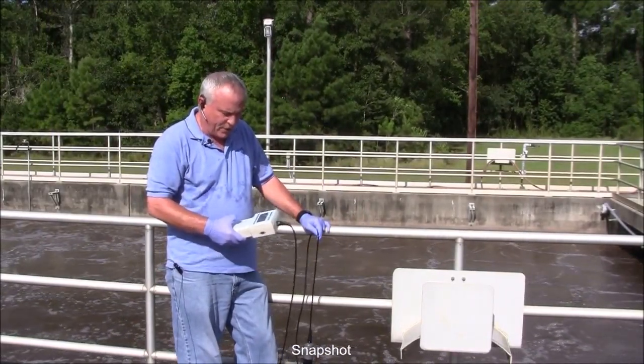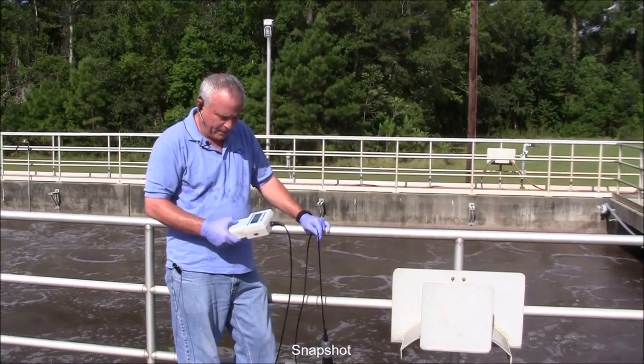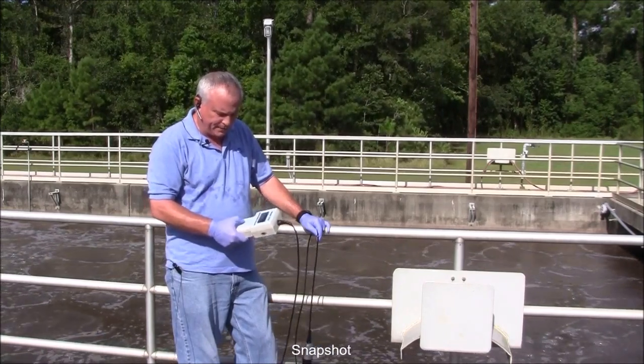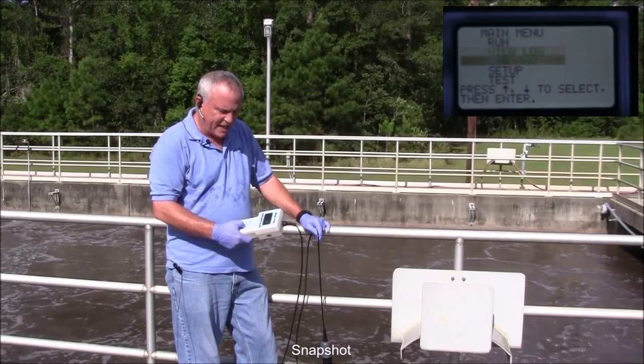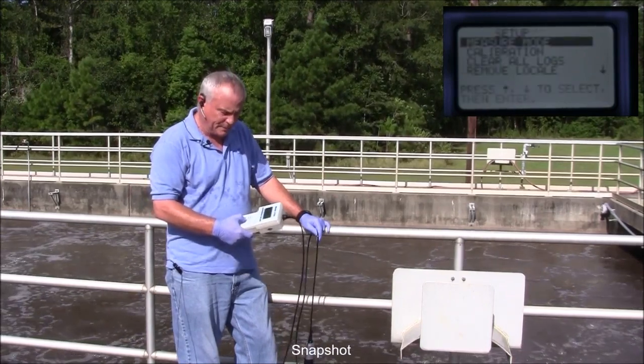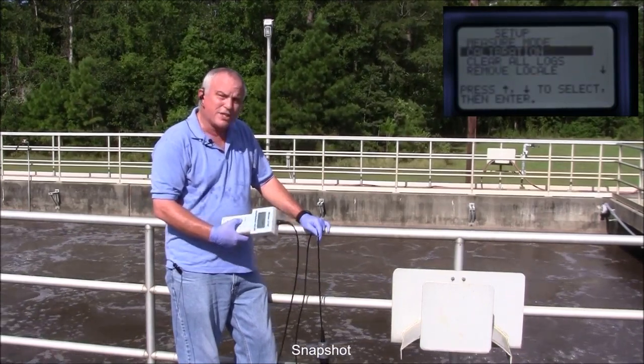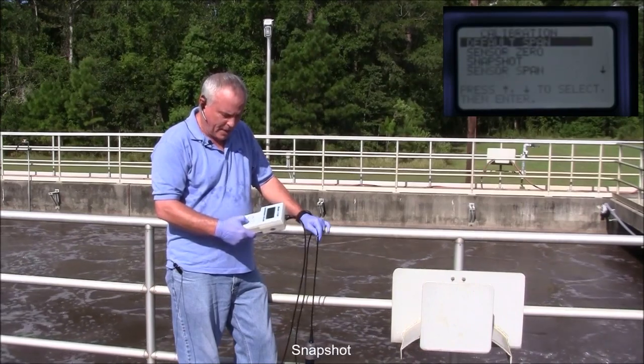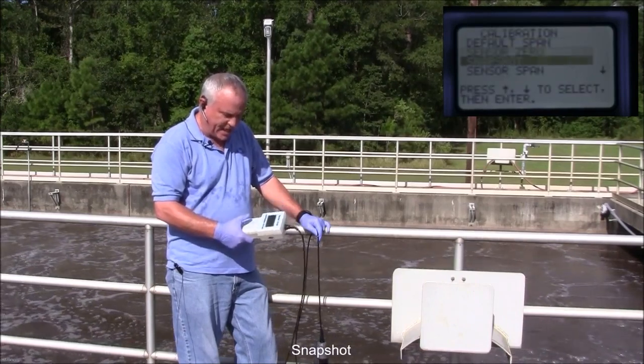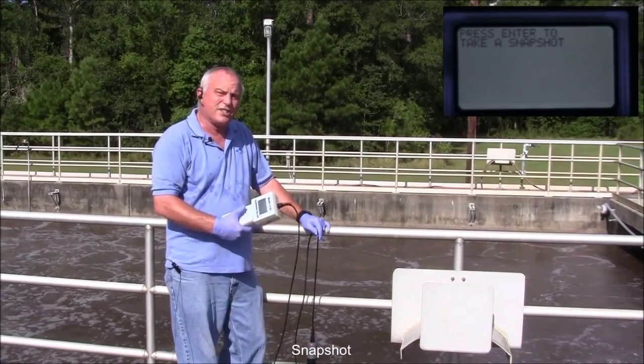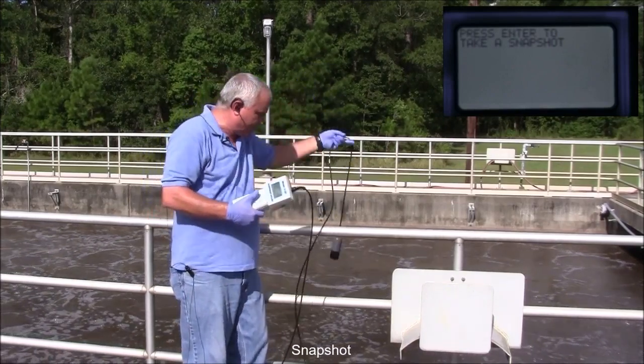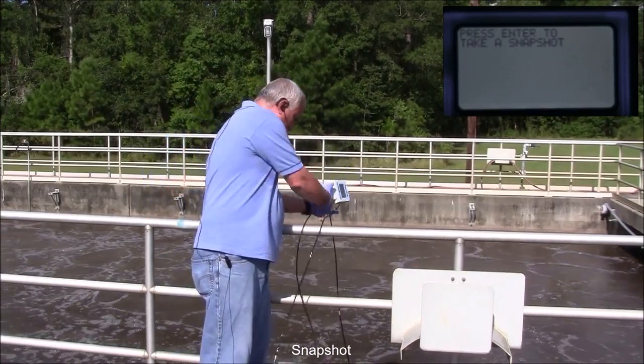The next step in the calibration is to do a snapshot. To do that, turn the unit on, press the menu button, scroll down to setup, press enter, scroll down to calibration, press enter, scroll down to snapshot, press enter, and it says press enter to take a snapshot. At that point, put the sensor down in the process.